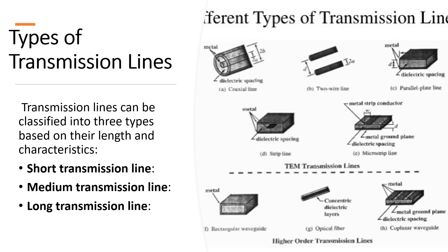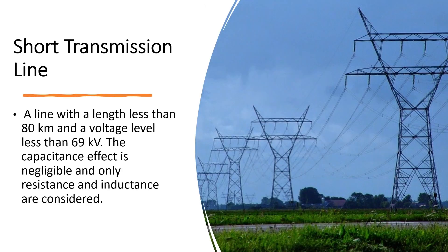Transmission lines can be classified into three types based on their length and characteristics: short, medium, and long transmission lines. A line with a length less than 80 km and a voltage level less than 69 kV is called a short transmission line. The capacitance effect is negligible and only resistance and inductance are considered.